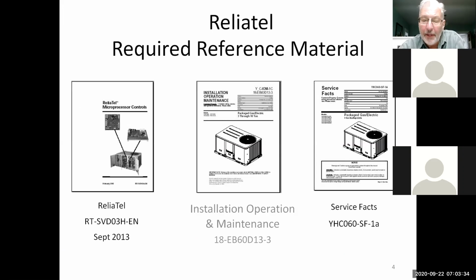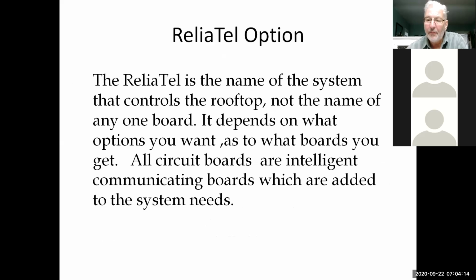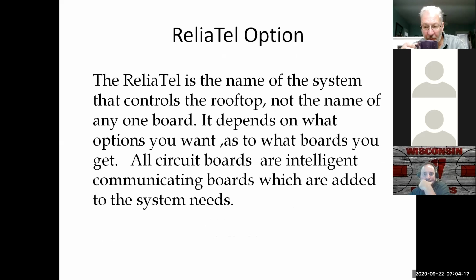The reference material that comes with the unit is the IOM, the installation, operation, and maintenance. Service facts are being phased out. They're all being incorporated into this installation book. But there's a book called Reliatel, and if anybody needs that book, shoot me an email or a message, and I'll make sure I send it out in PDF format. The Reliatel book is everything that you need to work on these units. It's about a 200-page manual, and it's got all the information to set up the operation. It's not found in the installation book, so if you need that, again, give me a call. We'll get that out to you.